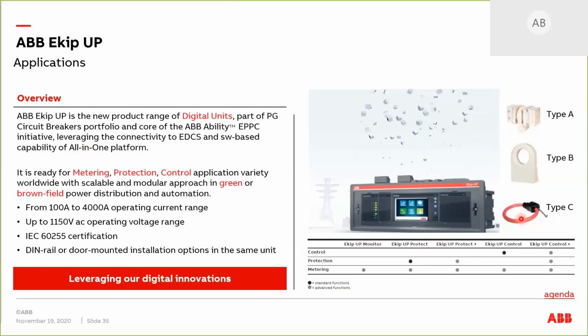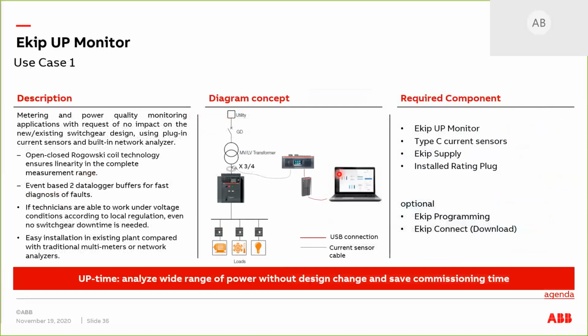So for the functions of the EKIP system, we have the case of the monitoring function. Let's say we have an ABB old circuit breaker here. Since it doesn't have the embedded technology or the EKIP trip unit technology, what we're going to do is put this EKIP Up on the system, and then we will use this breaker as the mechanical function, but the trip unit will be this one.